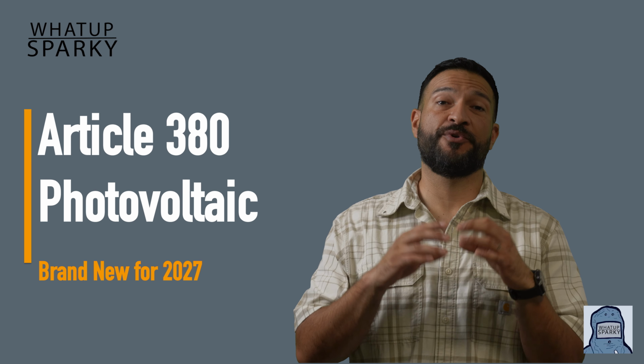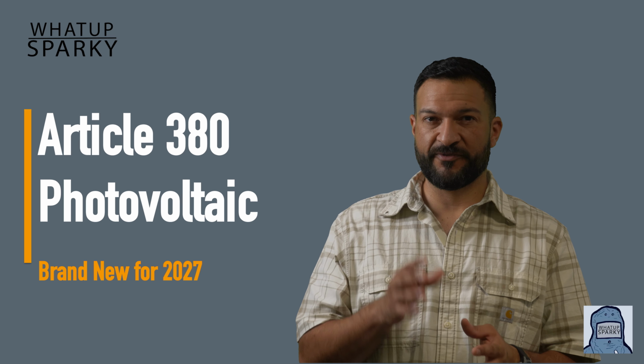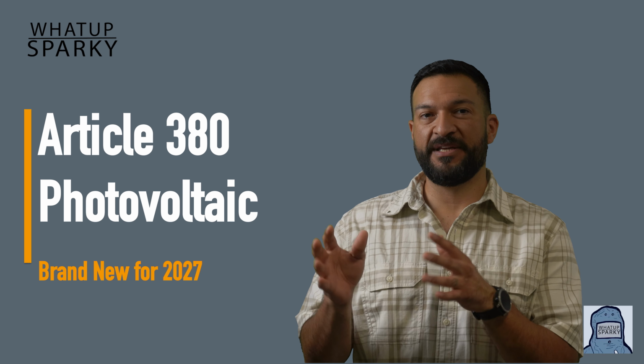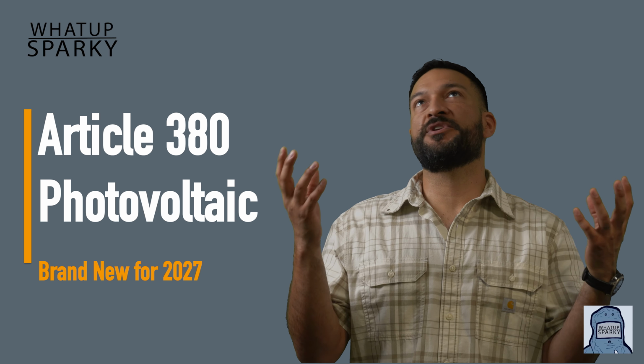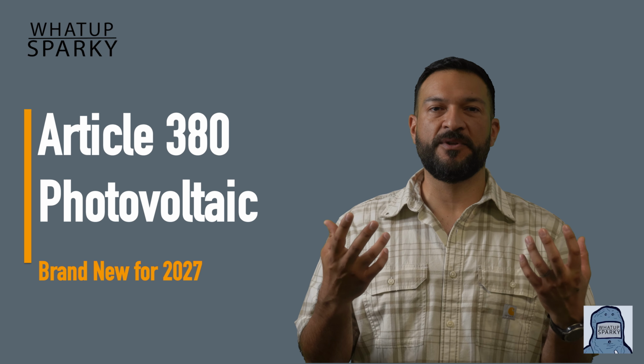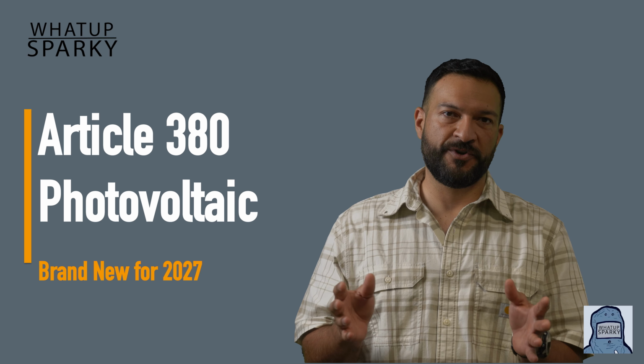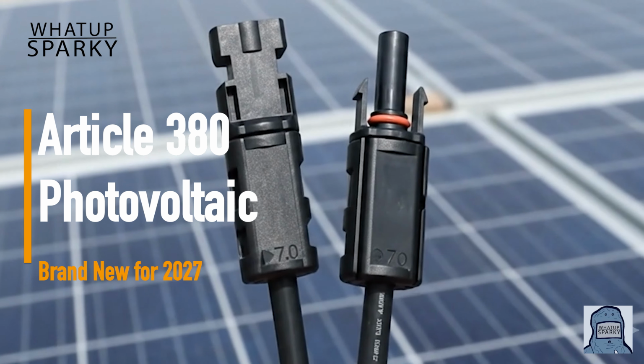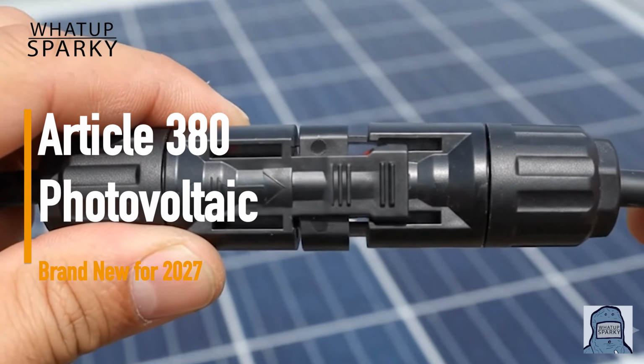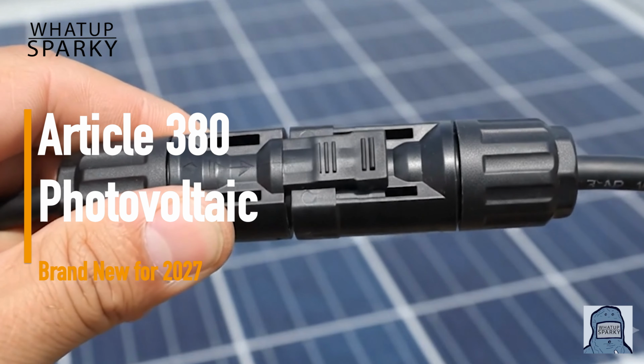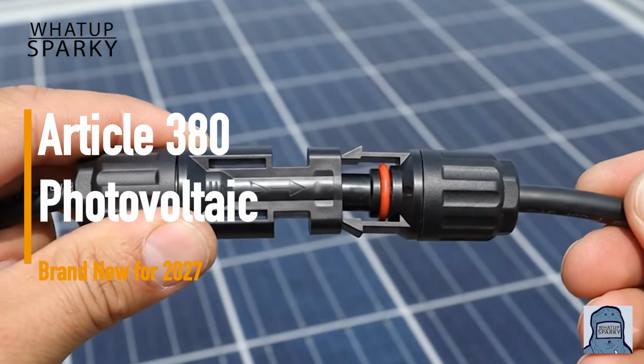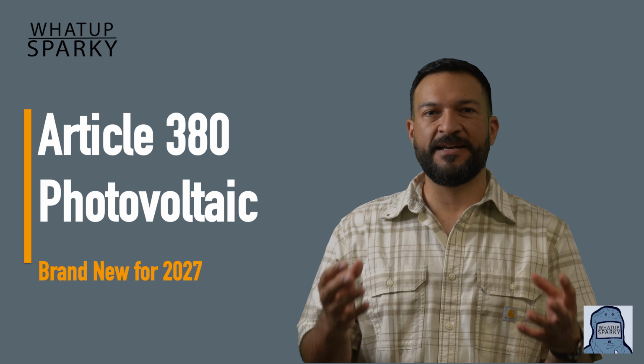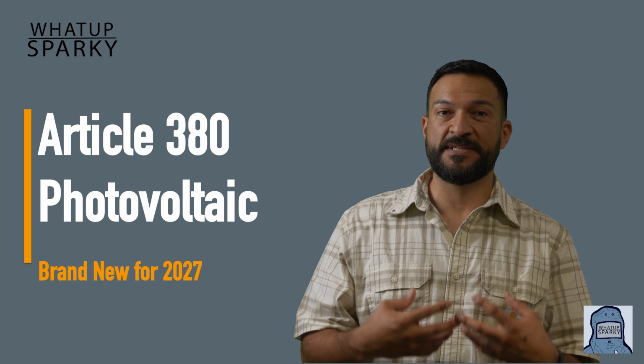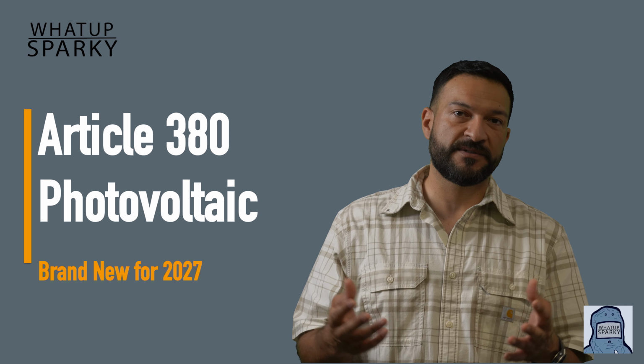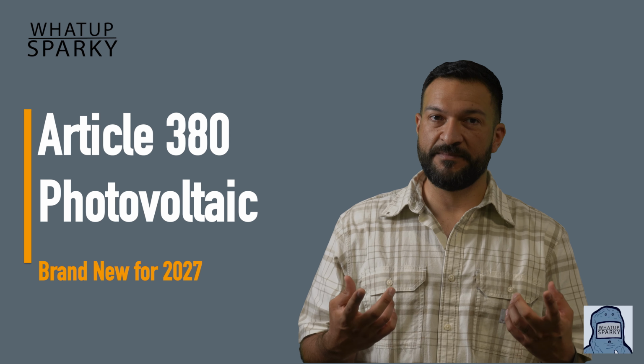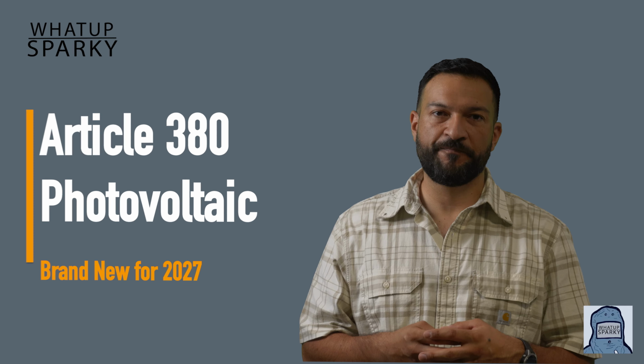The brand new Article 380, photovoltaic systems. First time 70E has a dedicated PV article. With the explosion of the utility scale and rooftop solar stuff, this fills a gap that was overdue. It had PV stuff in it before, but now we have its own chapter. So we'll cover the new requirements for risk assessment, before connector manipulation, the requirement to verify no load current before disconnecting, and the philosophy of continuously energized panels. So solar installers, O&M crews, decommissioning teams, you're gonna wanna pay attention to that one too.